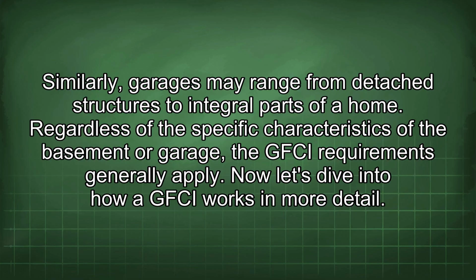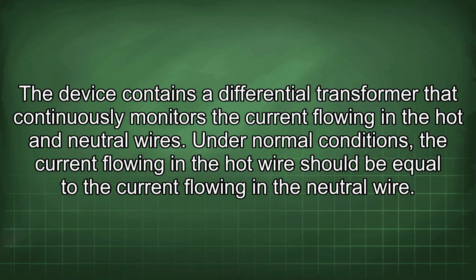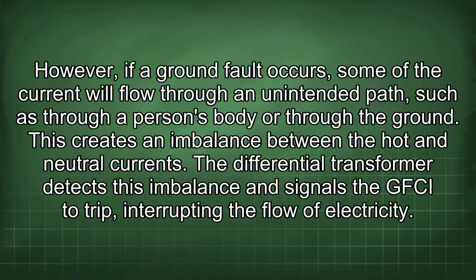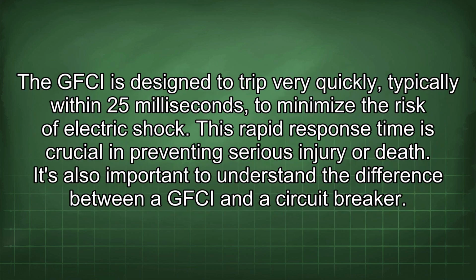Now let's dive into how a GFCI works in more detail. The device contains a differential transformer that continuously monitors the current flowing in the hot and neutral wires. Under normal conditions, the current flowing in the hot wire should be equal to the current flowing in the neutral wire. However, if a ground fault occurs, some of the current will flow through an unintended path, such as through a person's body or through the ground. This creates an imbalance between the hot and neutral currents. The differential transformer detects this imbalance and signals the GFCI to trip, interrupting the flow of electricity. The GFCI is designed to trip very quickly, typically within 25 milliseconds, to minimize the risk of electric shock.